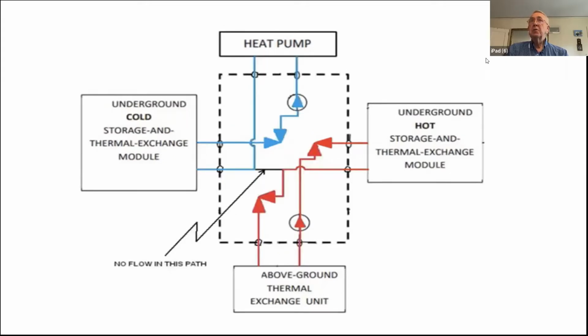On the opposite season, on the hottest summer afternoon, we're taking nice warm or maybe even hot water from the above ground unit, feeding it into the right-hand ground loop. And we're taking nice cool or cold water from the left-hand ground loop, feeding it through the heat pump to get efficient cooling for the building. So that kind of gives the benefit of what we were showing from the authors in Belgium.